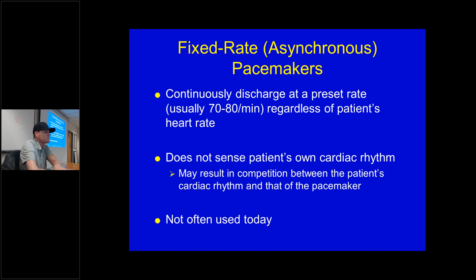If certain medication is given and their SA node for whatever reason starts to climb, it can compete with the pacemaker, and then both of them are going off. You got this tachycardic rhythm because the pacemaker is not stopping, even though the regular heart is still conducting. All right, those kind of pacemakers are kind of on the outs, obviously, because they're less effective. So demand pacemakers only switch on to the default pace when the SA node fails, right? When it gets too slow. And then the pacemaker's preset rate starts up.